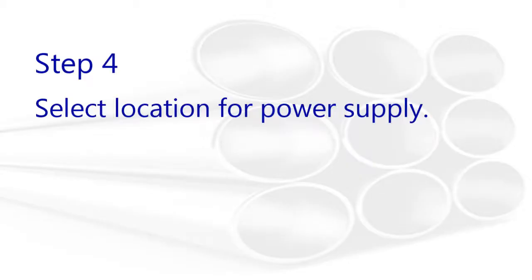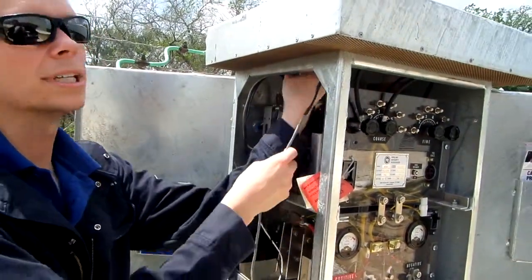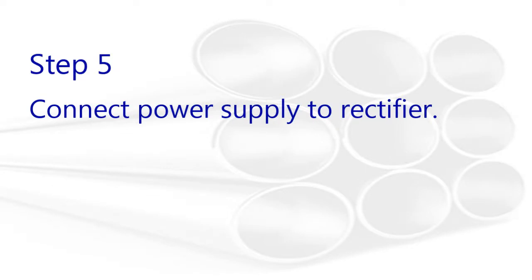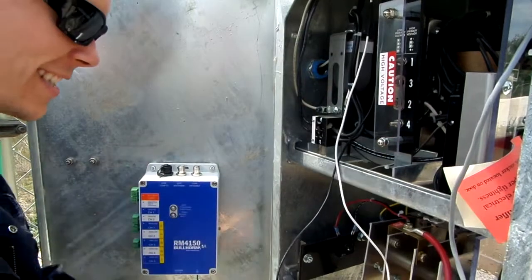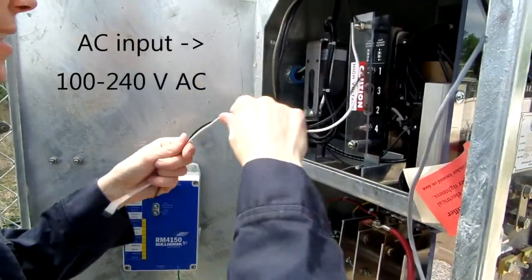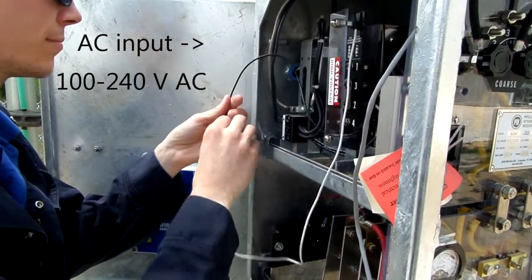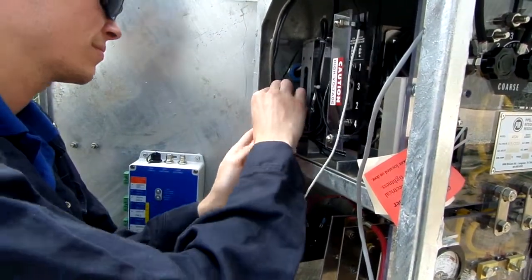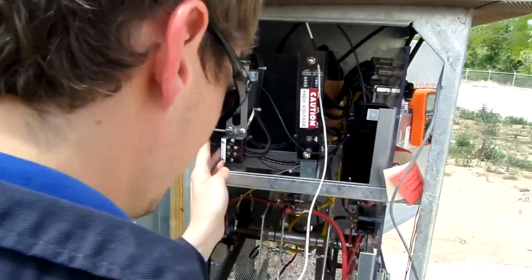Select a location where the power supply will be installed. This location should also be easily accessible. Connect the power supply to the rectifier. If you are using an AC to DC power supply, connect the power supply's AC input cable to a 100 to 240 volt AC supply or breaker. A DC to DC power supply can be purchased from American Innovations if an AC power source is not available.